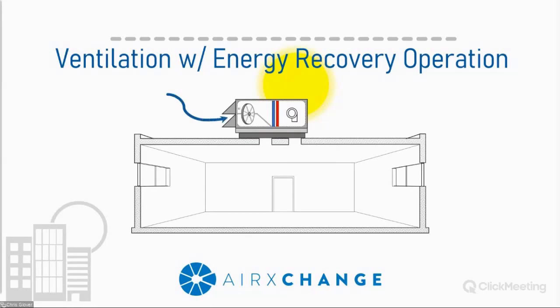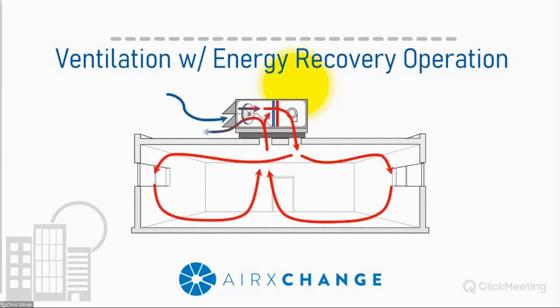So you're performing the same process, but I often refer to energy recovery as a load shift. You're essentially shifting the conditioning load of the ventilation air from the primary heating element over to the energy recovery device that is conditioning that air using the low-grade thermal energy that's normally exhausted outside the building. By using the low-grade energy instead of a high-grade energy like a gas or electricity, it greatly reduces the amount of energy consumed to treat the same amount of ventilation air.